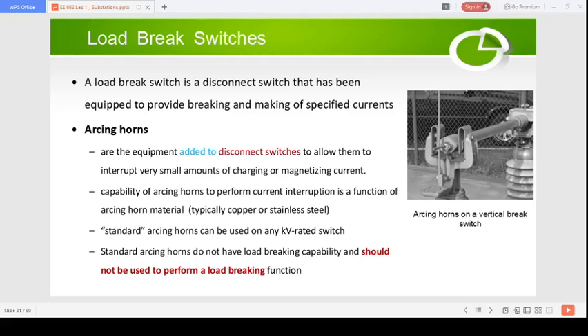Load break switches. The load break switches are a special type of disconnect switch that has been equipped to provide the breaking and making of a specified current. There is a device called arcing horns attached to the disconnector or the isolator. It allows the isolator to interrupt a very small amount of charging or magnetizing current.